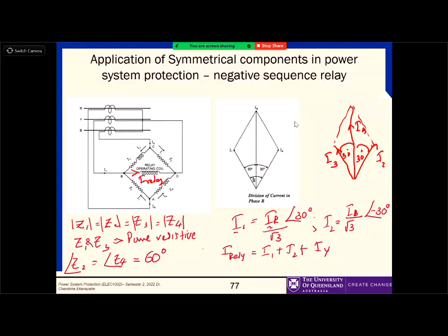That will cause some overheating in the generators, because it produces a set of currents which oppose the normal currents. Because of that, the generator armature temperature is going to increase. If you detect a significant amount of negative sequence current in the system, and the generator winding temperature is going up, you can correlate those two and identify issues related to that.